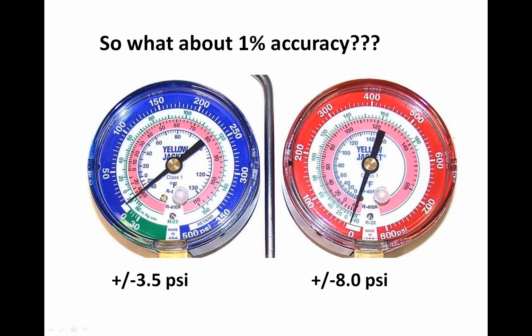And even though they're 1% accuracy gauges, it still doesn't eliminate the characteristics of a gauge, that it's still most accurate in the center of its span. So again, if we're using this gauge right here from a typical R22 application, which would typically be somewhere around a 40-degree coil, right? We're not near the center of the span of that gauge. If we're in a 410A application, now we're still at that 40-degree coil. We're right here, and we are at the center of the span of that gauge. So even though it's a 1% accuracy gauge, you're still not going to be as accurate if you're using that same gauge for an R22 application. If we look at the high side gauge, now we did gain a little room there. 1% of 800 is 8 psi, so we did gain some ground there. So let's look at how that influences operation.